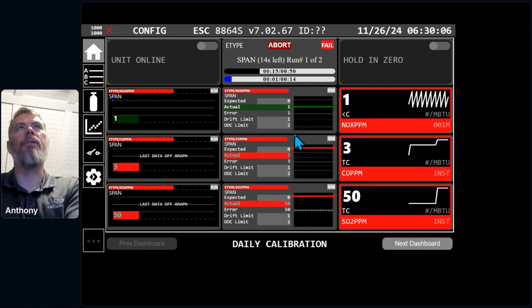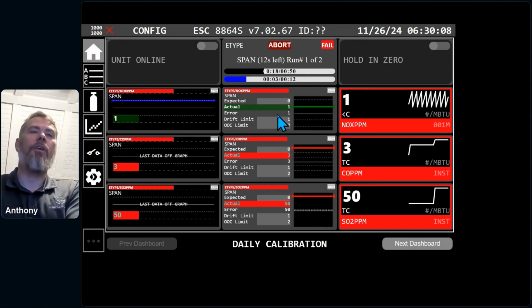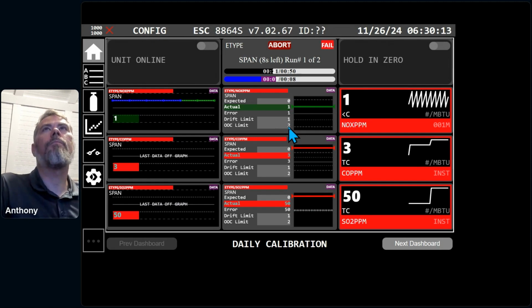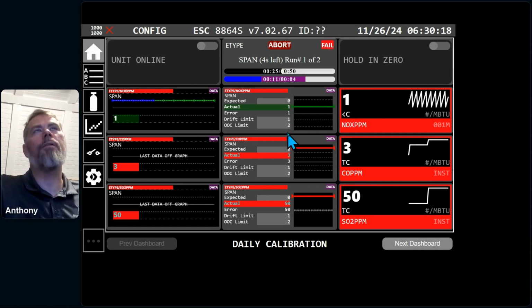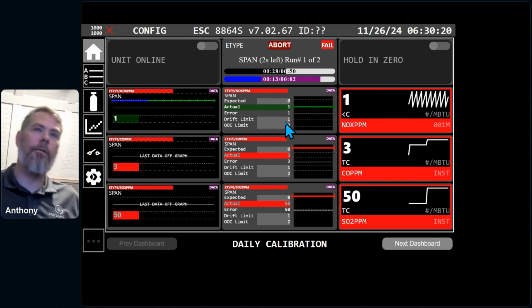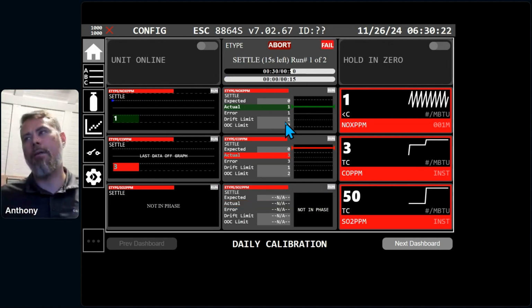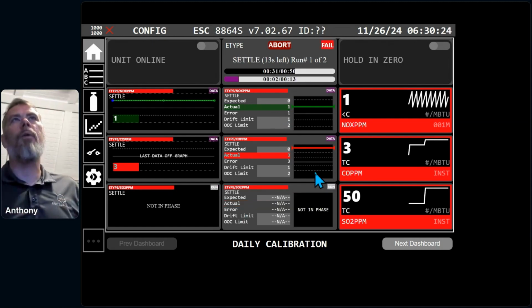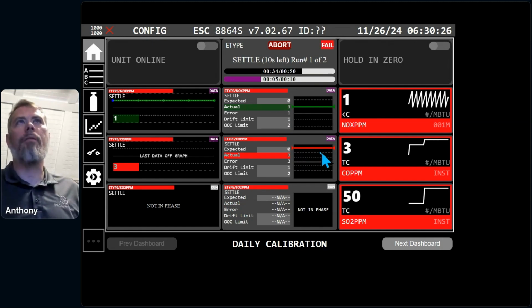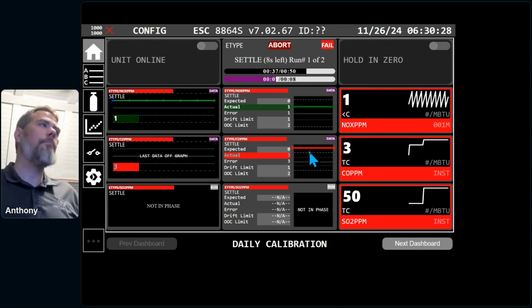Oh, and you'll see that the error is infinite there because that channel doesn't have a span configured on the channel. So not a proper configuration for that type. But yes, it will show percent, and it shows what's configured, not what the number is. However, we do a calculation and evaluate what that number should be to put the line in the proper place on the graph.